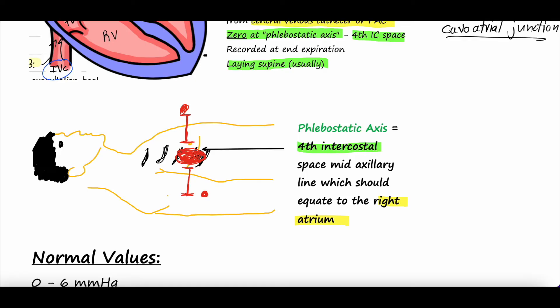You want to zero the pressure right at the phlebostatic axis — at the right atrium. If you zero it too low, the measurement will read falsely high by that offset; if you zero it too high, the measurement will read falsely low. It needs to be zeroed right at the cavo-atrial junction. The phlebostatic axis is at the fourth intercostal space, mid-axillary line — the armpit midline — which is about where the heart lies when a patient is on their back.